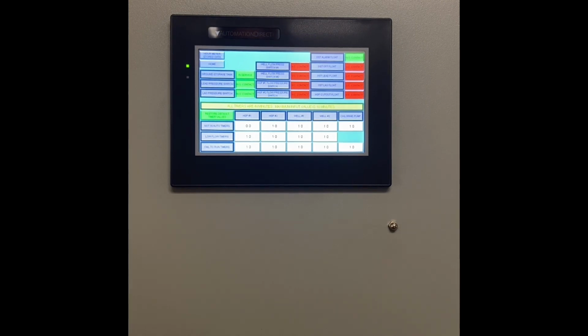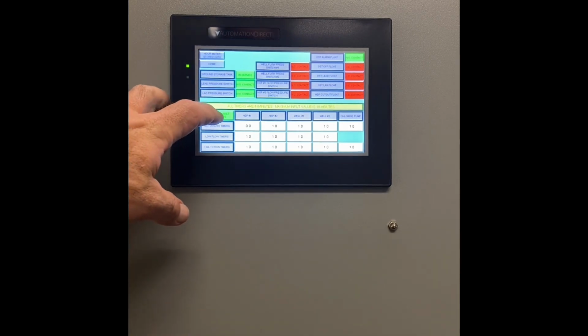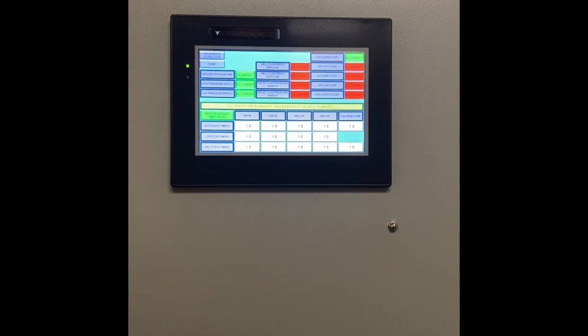So what happens if you change that and you go, oh no, I don't remember what I should have it as? I put a restored timer value right here. And you see it went back to 1. 1 is a fairly liberal amount of time to work with. I would imagine that the times will actually be on the orders of 0.2 or 0.3 minutes at best for each of them. We'll get into how and what each of these failures go into when we get back into the main screen in a minute. So we'll do that now.